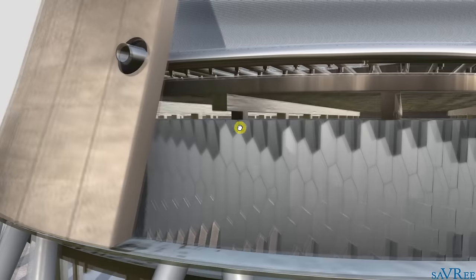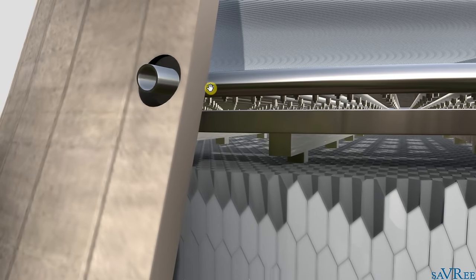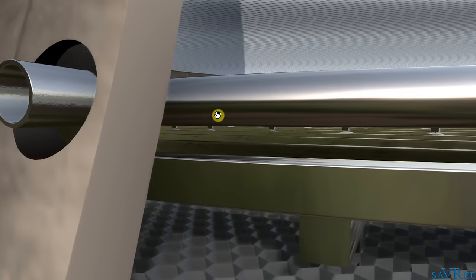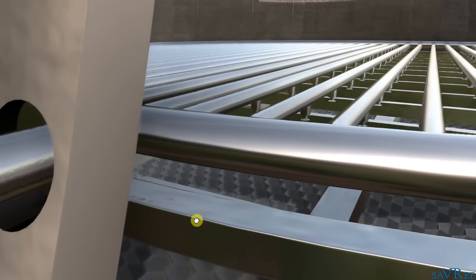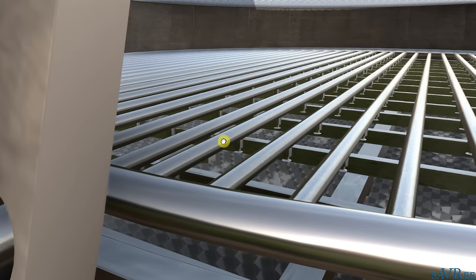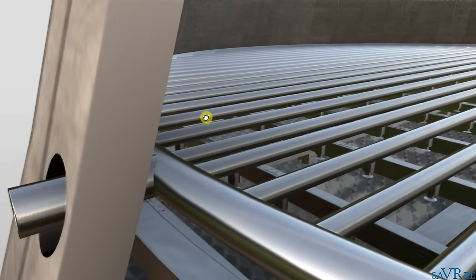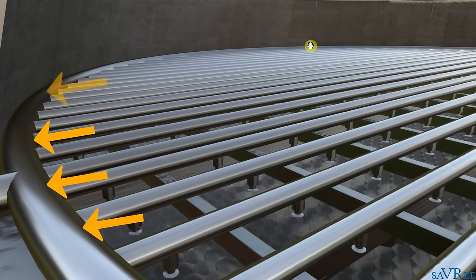We need to be able to condense that steam and turn it into condensate in order that we can pump it back to the boiler. So how do we cool down the water? Well, the water is returned, and it passes to this pipe here. And as we can see, there is actually a distribution manifold. I'll just take the angle from the top. And we can see we have a series of pipes here. We have one main ring that goes around the outside. Just come across. So here is the main ring, goes around the entire cooling tower.